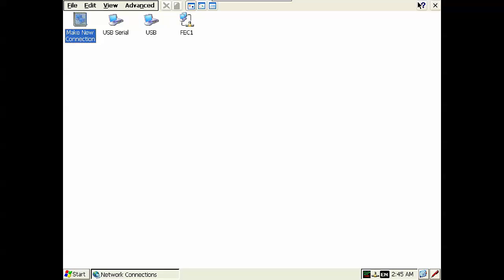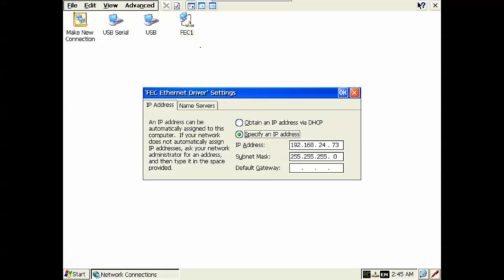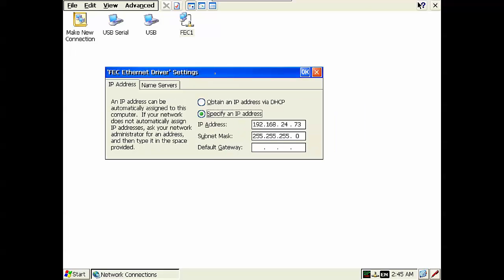From here if we double click on the FEC1 network connection you can see the settings to put in the IP address. I've specified a hard IP address of 192.168.24.73 for my QuickPanel. Of course you can always set your QuickPanel up to obtain an IP address automatically via a DHCP server.